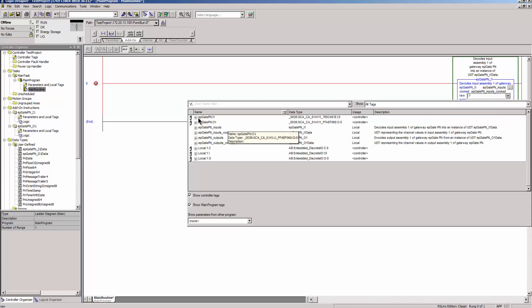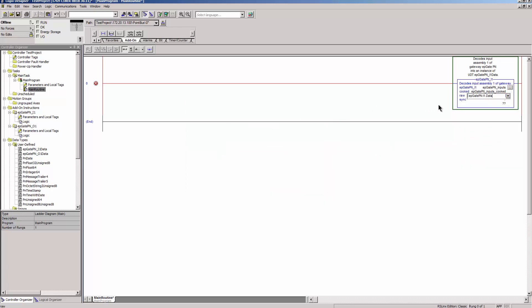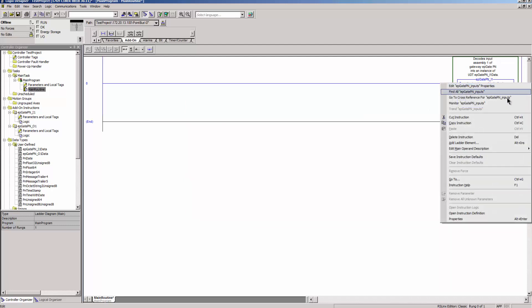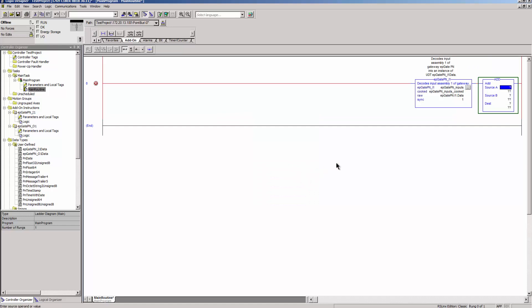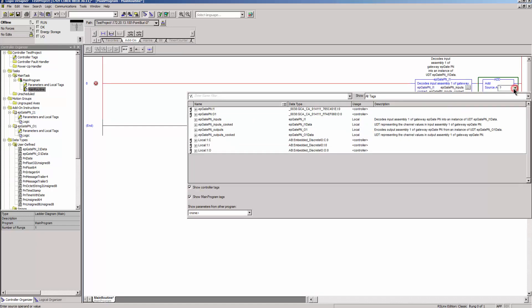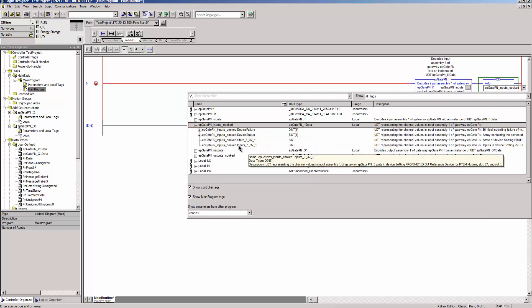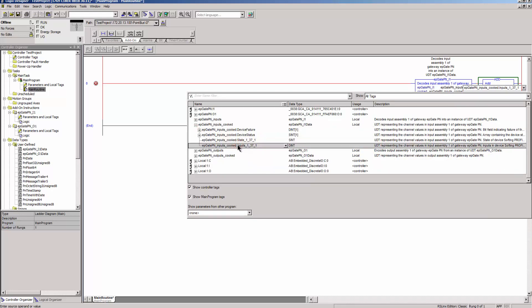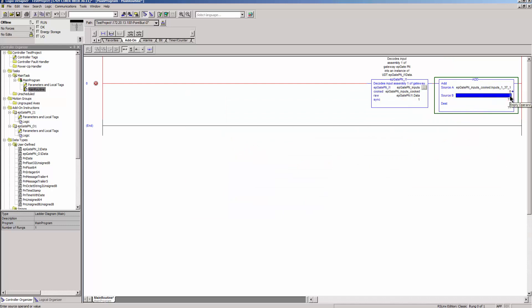The read input data can now be incremented by one. This requires the Add block. Right-click and select Add Ladder Element and then Add. Connect Source A to the input data and enter a 1 in Source B. Under Dest, select the output data.